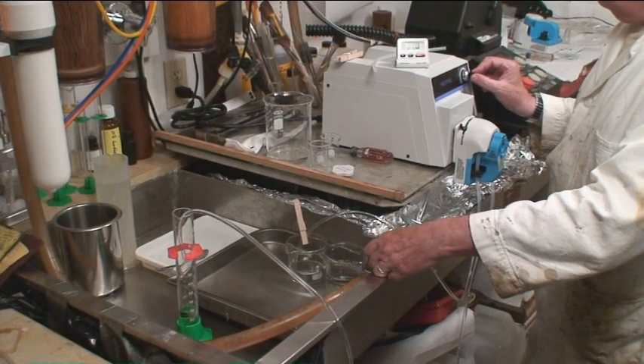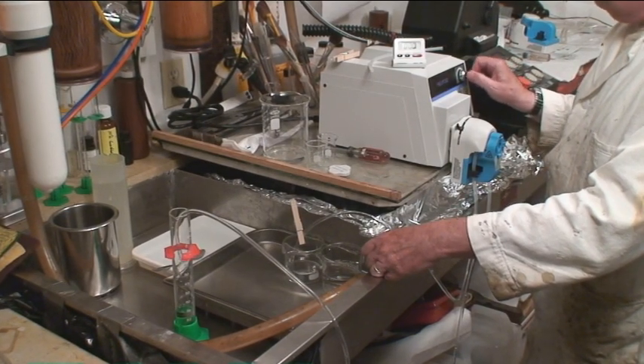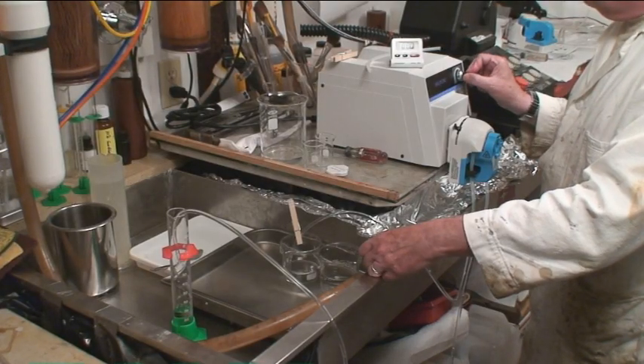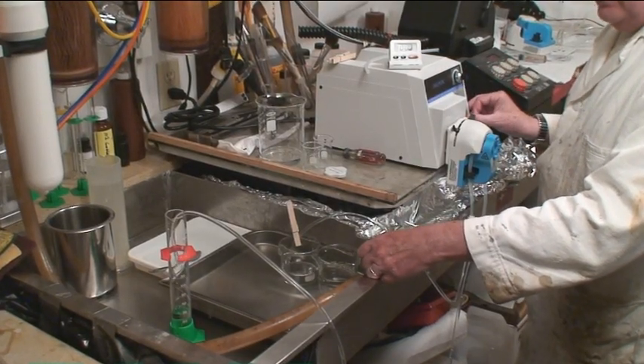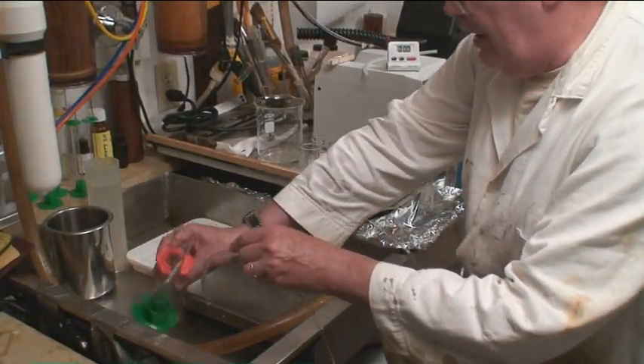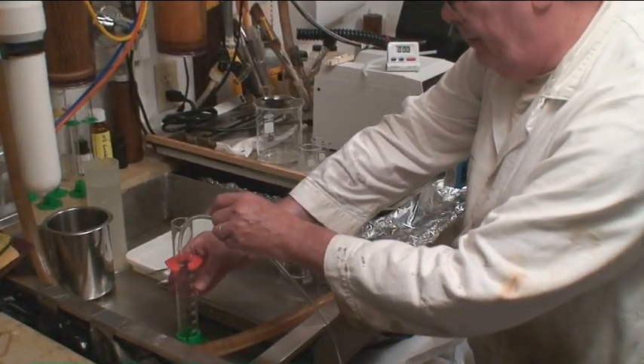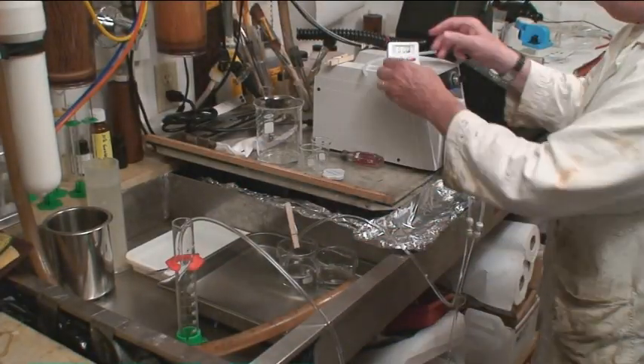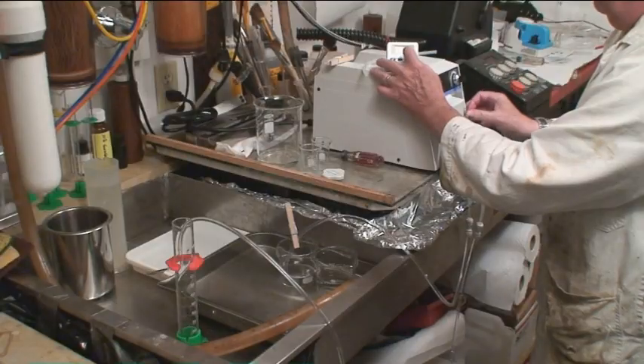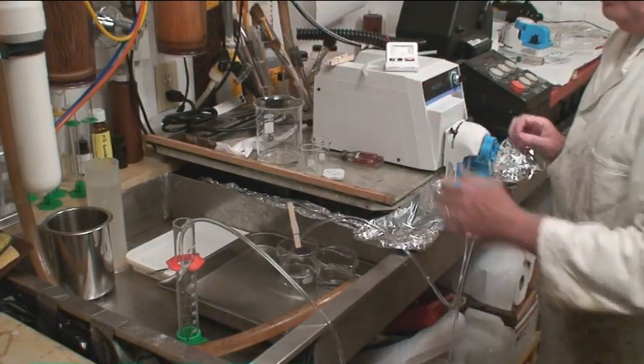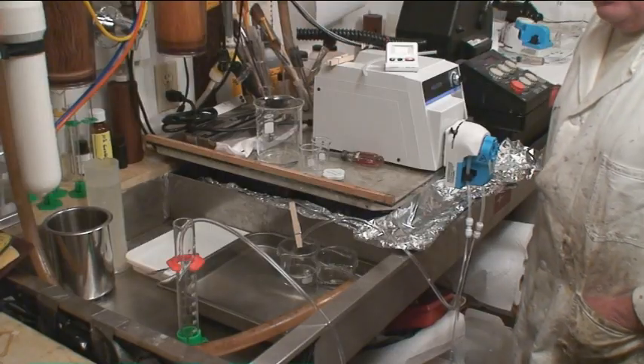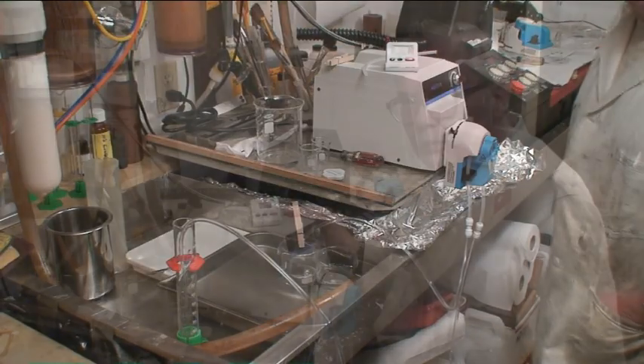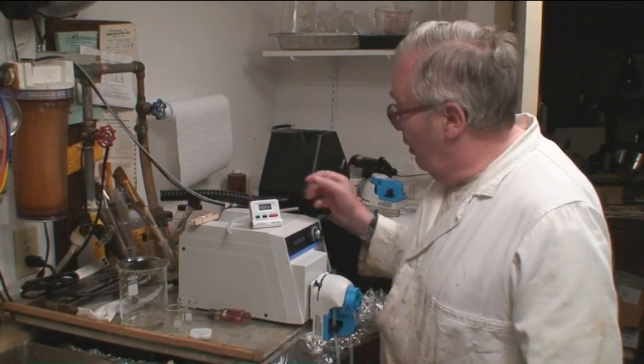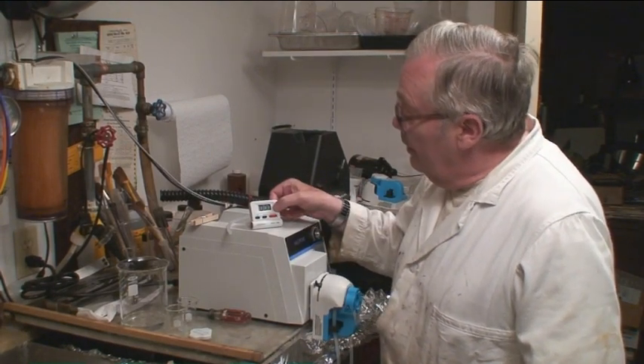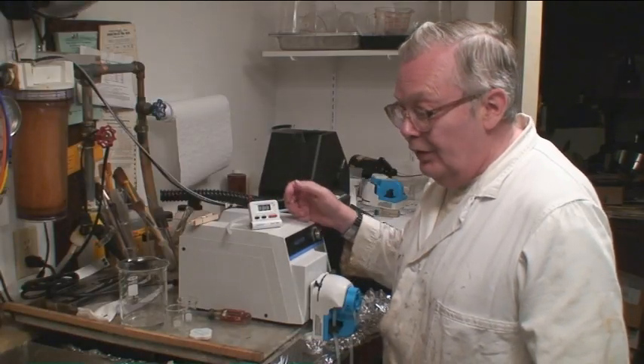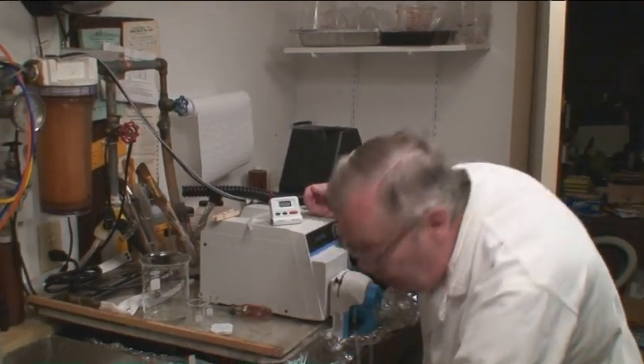The next thing I would do is to turn this up 1 unit higher and turn it on again. But in doing so, I also have to empty the graduate cylinder. So I begin by setting another minute and by starting. And this is running at a level of 2 on the meter here. At this setting of 2, in 1 minute, the pump has delivered 100 milliliters of water.